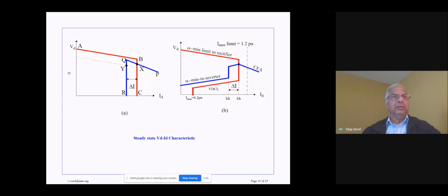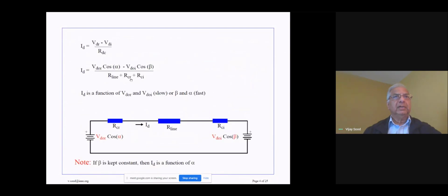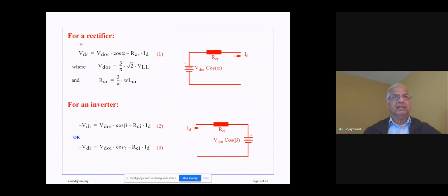All right, so how do we implement that control strategy? In this graphic over here, we have the rectifier shown in red and the inverter in blue. So let's talk about the rectifier side controls first. This graphic shows you the VD-ID characteristic of the controls. Now, the line AB represents the rectifier operating with minimum firing angle alpha. This is a direct extraction from equation number 1. So this is a direct implementation of that.